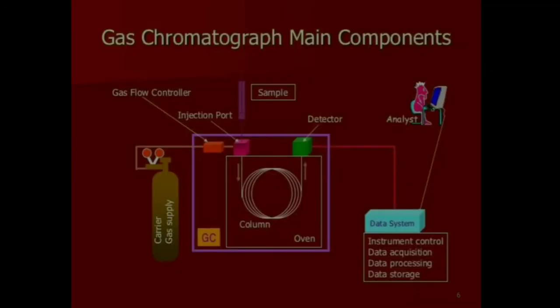Here we have the complete setup of gas chromatography. Starting from the carrier gas supply, which is connected to a gas flow controller. This gas flow controller is connected to a sample injector port, one end of which is connected to the column in the oven. The other end of the column is connected to a detector outside the oven. This detector is further connected to a data system where data acquisition, data processing, and data storing are performed.